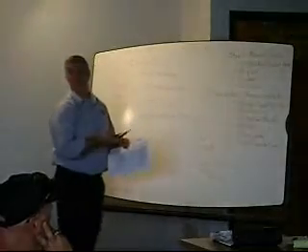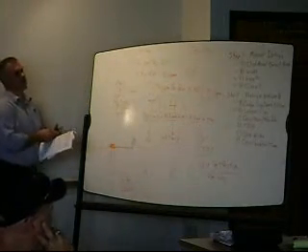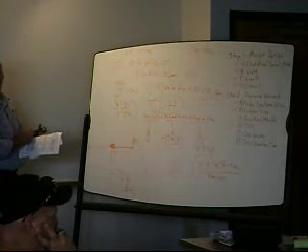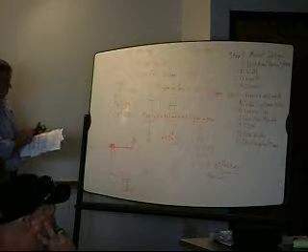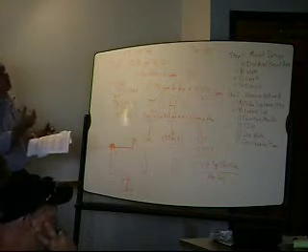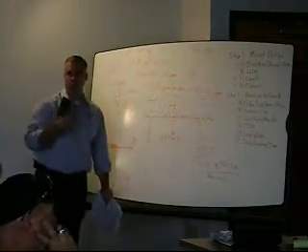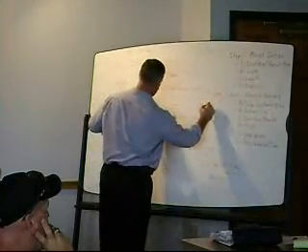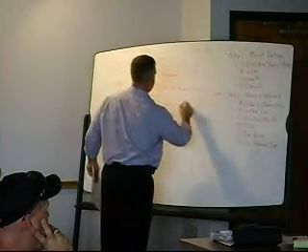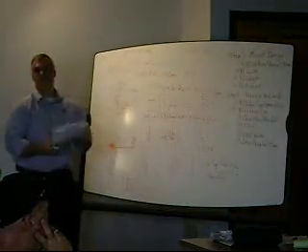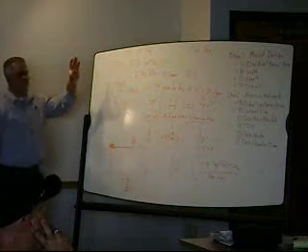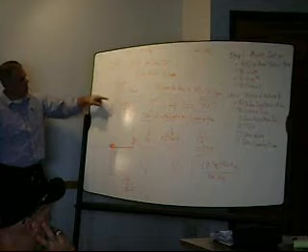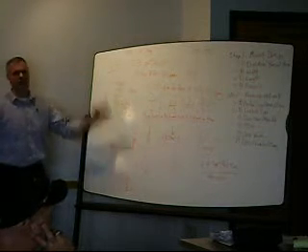go to his. I've got 21 feet of total dynamic head, based on adding that together. 21 feet TDH and 31 GPM. Now it's time to choose the pump. You designed your mound, designed your sand, width and length. You designed all your holes, your laterals, your spacing, your size, your force main. You got it all figured out.